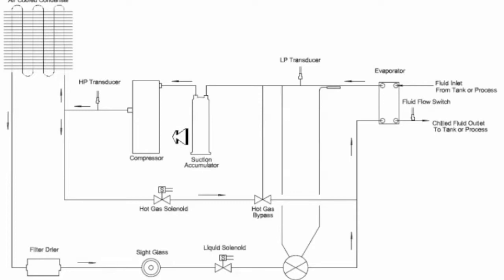Now on a legacy chiller, 90 seconds after the compressor starts, by default, this hot gas bypass solenoid will open, allowing hot gas up to the inlet of the regulator. You'll also notice that there's a tube here that connects up to the chiller system's suction line. Now, this allows the hot gas bypass regulator valve to know what the suction pressure is up here.